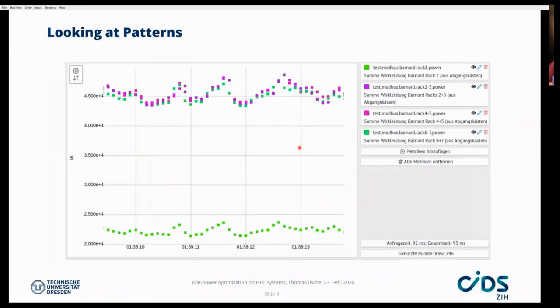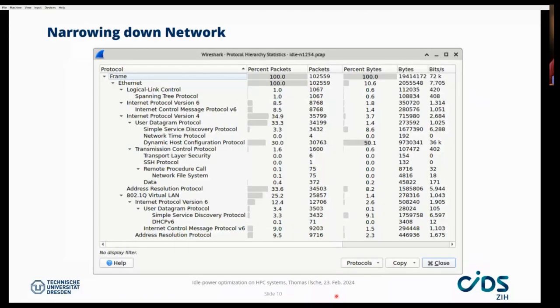And actually, we can see this at an even more fine-grained level. Now we are looking at one line here being 1 second apart. And we see these 200 millisecond measurements. It's actually because there are sums of those, there are a little bit more than 200 milliseconds. But we see that even inside 1 second, the power consumption of all racks follows a synchronized pattern. And so this can only happen if you have a common cause for the increased power consumption that's very tightly synchronized. And this is, of course, here the network.